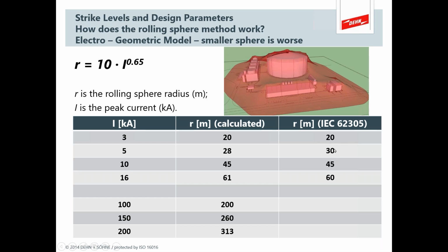IEC methods allow you to pick a smaller radius if you're being more diligent for a higher risk evaluation. That's really the purpose of the rolling sphere concept, it models what a lightning step leader looks like and how worried you should be about it reaching into the nooks and crannies of your structure. If you had a building full of gasoline, you wouldn't want that to be a source of ignition, so you'd apply more lightning rods to prevent a strike there. This gives you flexibility and intelligence in selecting protection methods.